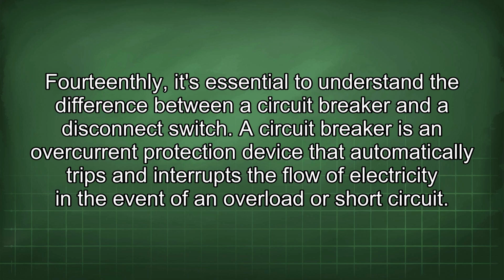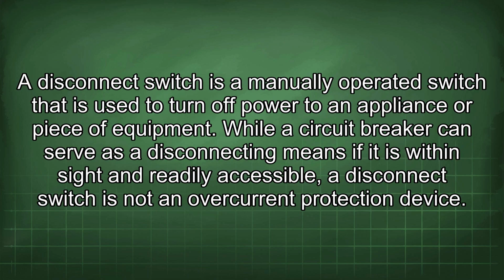A circuit breaker is an overcurrent protection device that automatically trips and interrupts the flow of electricity in the event of an overload or short circuit. A disconnect switch is a manually operated switch that is used to turn off power to an appliance or piece of equipment. While a circuit breaker can serve as a disconnecting means if it is within sight and readily accessible, a disconnect switch is not an overcurrent protection device.